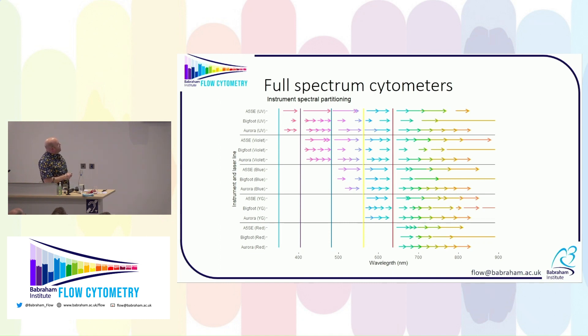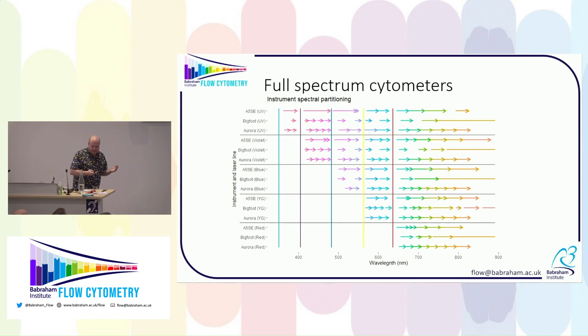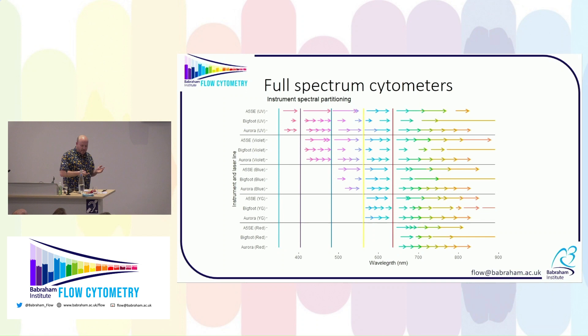The Aurora has lots of roughly 14 nanometer filters, not so much in the blue areas. The Bigfoot has more detectors in the yellow-green area but less in the violet. The A5SE has almost no separation in filter patterns in the UV regions, but a lot in the violet because obviously they have all the BV dyes. Interestingly, the Bigfoot and the A5SE look like a traditional flow cytometer in the way they segregate their spectra.